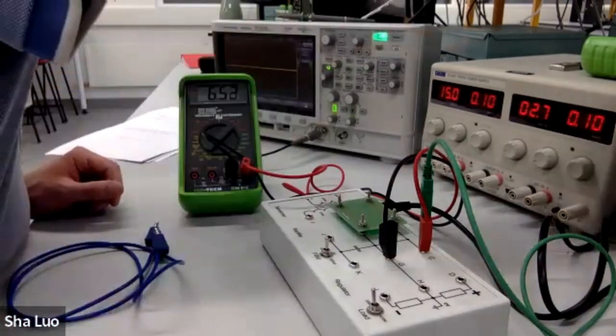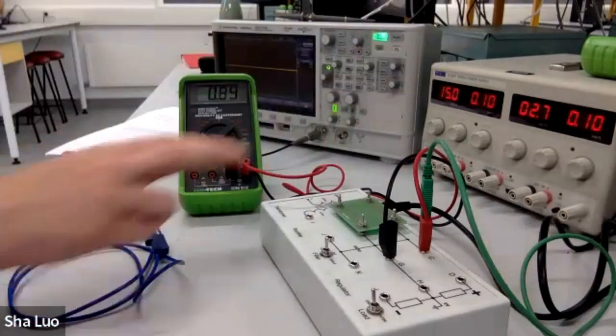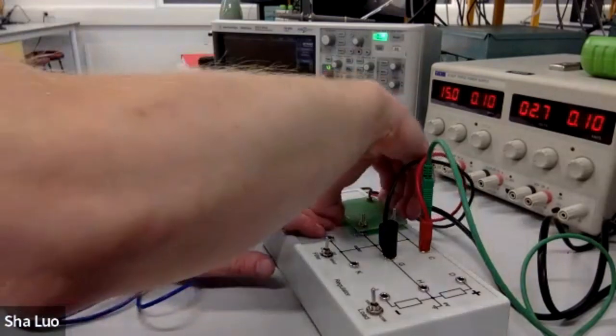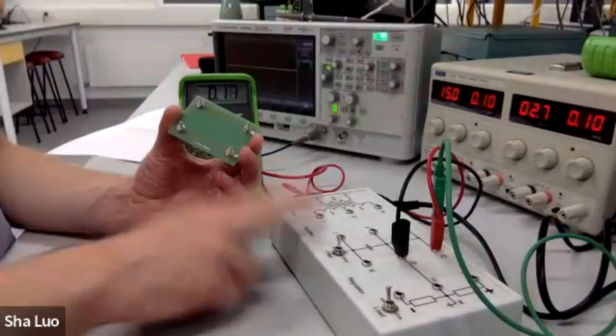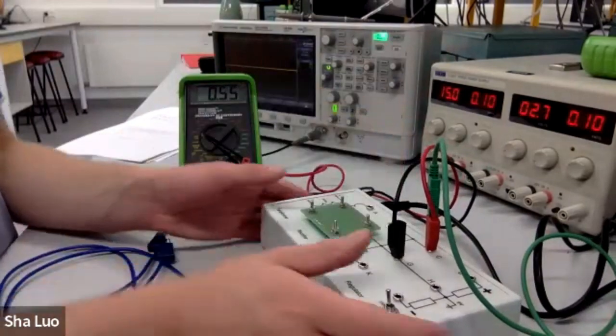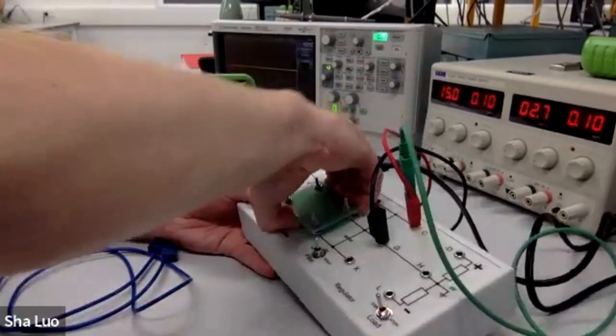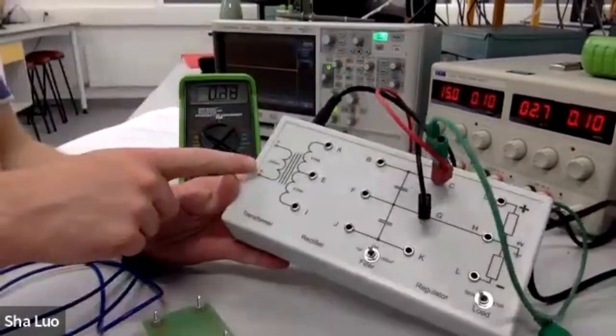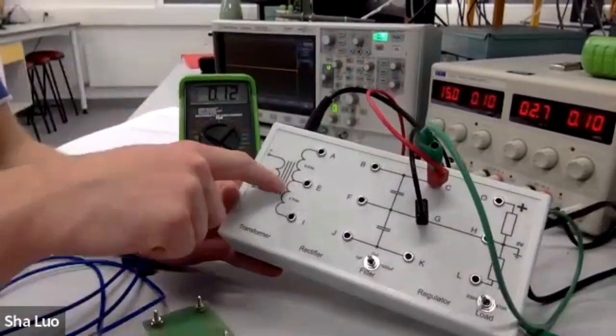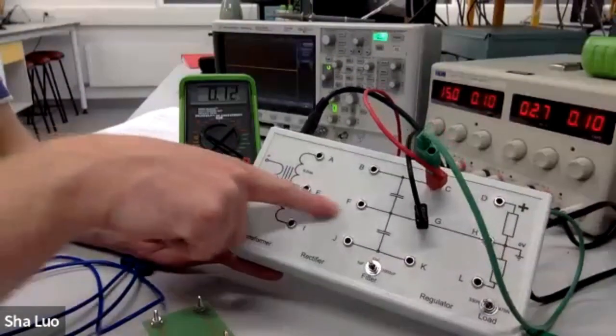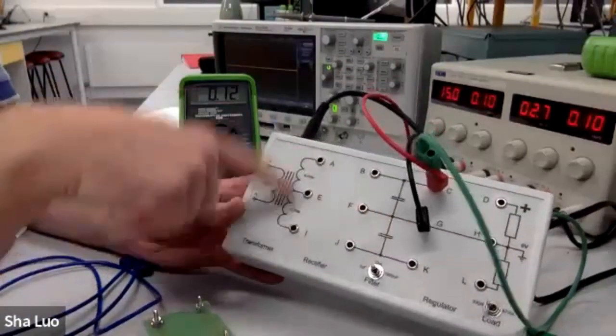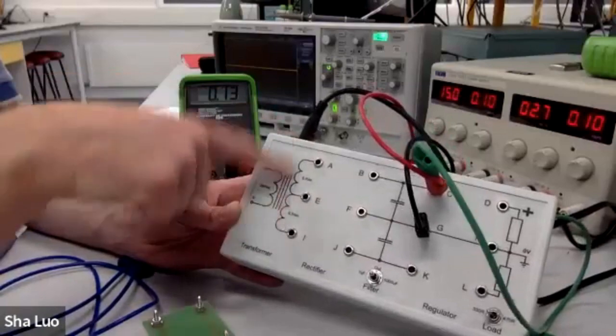If I turn the power off, we can repeat this for the other secondary winding. So I remove the link card from the power supply module and plug it in at the bottom. This is a center tapped transformer, as you can see denoted here, so this center rail is effectively our ground reference, and these 2 ends are our 2 output voltages.